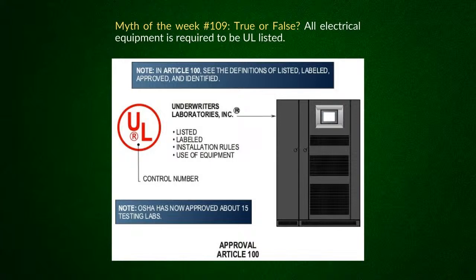Then if you look at 110.2, it says all your equipment has to be approved. When you look at the definition of approved in Article 100, it says acceptable to the authority having jurisdiction. So a lot of times, in the oil fields and elsewhere, companies like Exxon, Mobil, British Petroleum, Arco, Texaco sometimes design their own equipment—they probably know better than the UL standards know. They'll design that equipment to make sure it meets their needs and is installed in a safe manner, and since they're the authority having jurisdiction, they're the ones who give approval of the equipment. That's nothing uncommon.